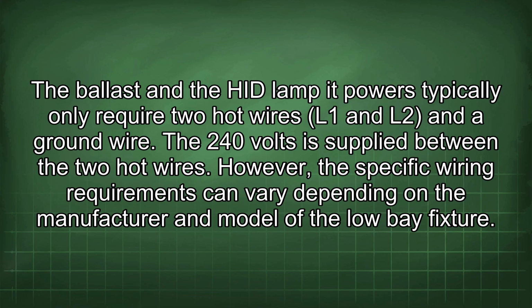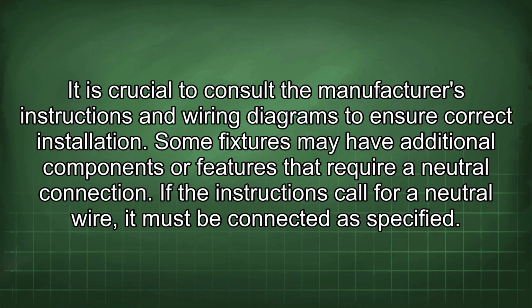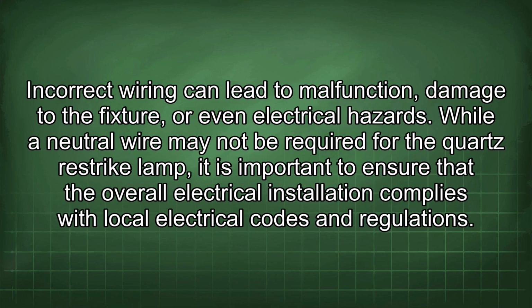However, the specific wiring requirements can vary depending on the manufacturer and model of the low bay fixture. It is crucial to consult the manufacturer's instructions and wiring diagrams to ensure correct installation. Some fixtures may have additional components or features that require a neutral connection. If the instructions call for a neutral wire, it must be connected as specified. Incorrect wiring can lead to malfunction, damage to the fixture, or even electrical hazards.